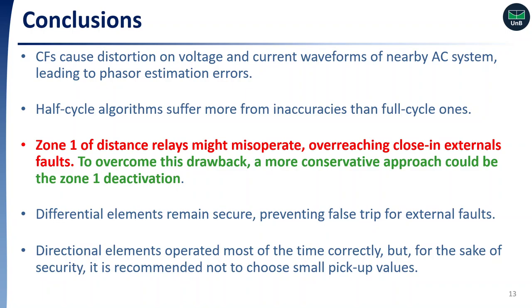Differential elements remain secure, preventing false trips for external faults in all evaluated cases. Directional elements, in turn, operate correctly most of the time, but for the sake of security, it is recommended not to choose small pickup values. Last but not least, it is noteworthy that even though errors in phasor estimation of AC voltage and current always arise due to LCC-HVDC transient response, relays do not always misoperate. Even so, since the LCC-HVDC transient response is unpredictable to some extent, it is recommended to thoroughly evaluate the performance of line protection functions using ATP/EMTP-based software or real-time simulators, instead of only using phasor-based simulation software as has been traditionally done by protection engineers.